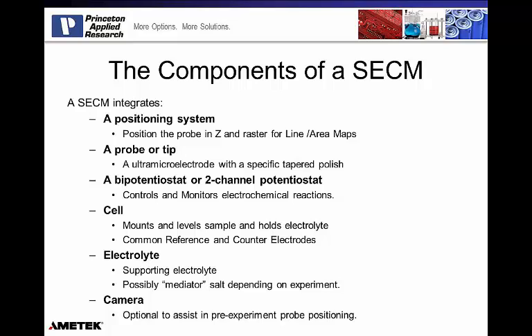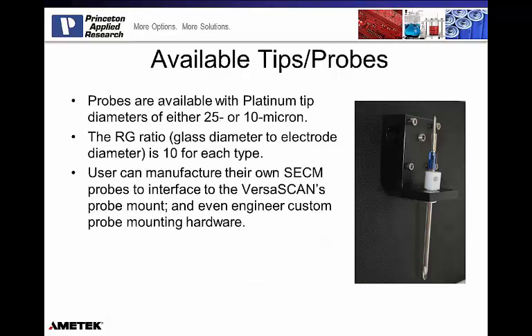I'm going to call out a camera as an optional accessory. This is a nice thing to have, especially in the beginning as you start doing the SECM experiments, because you want to position the probe close to the sample surface, but we don't want to contact the sample surface. And a camera helps us do this just visually as it magnifies the probe and the sample, and as the probe approaches the sample. But we also have an electrochemical way to do this called an approach curve that we're going to talk about very shortly.